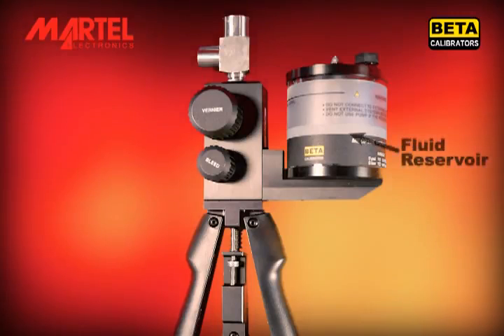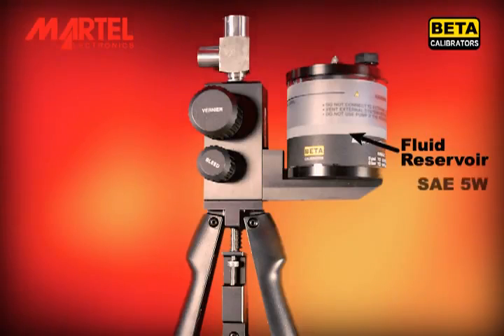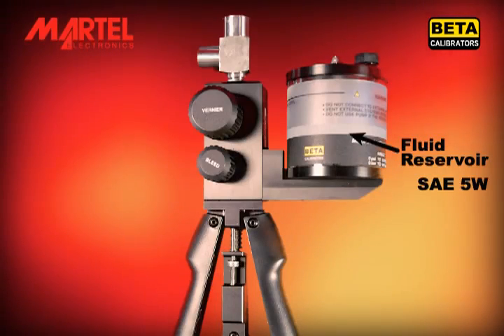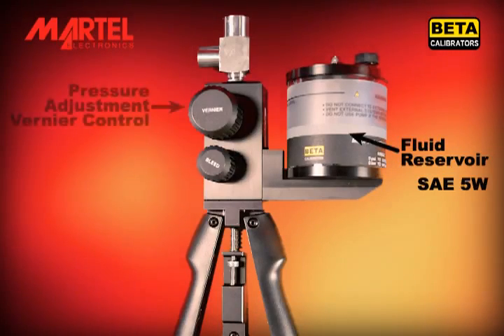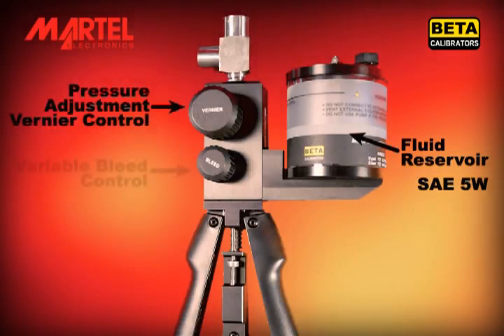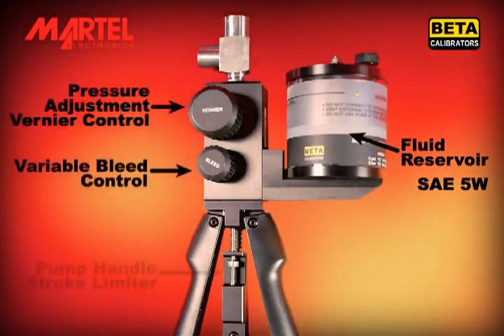There is a fluid reservoir for deionized water, mineral oil, or light hydraulic fluid, such as SAE 5W. The choice of media is important. A high viscosity fluid will not work and may damage the pump. On the side are the pressure adjustment vernier control and the variable bleed valve for pressure release.